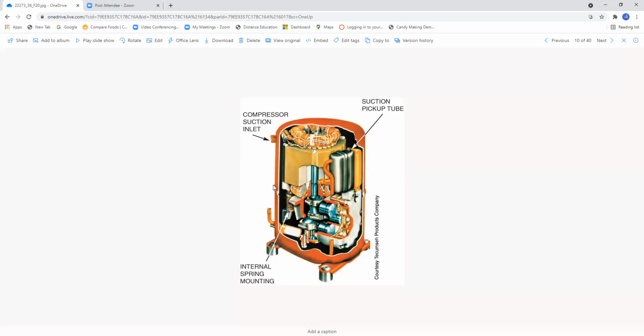I have taken these things apart for just inspection. It's an awful lot of work. So typically when a compressor fails, just figure out what the failure was. Was it electrical or was it refrigerant related? Make the necessary corrections and install a replacement compressor. These compressors are very reliable. They do a very good job. I technically prefer the scroll design over the piston, but these work very well. This particular one here is made by Tecumseh. It's a company that's been around for a long, long time.